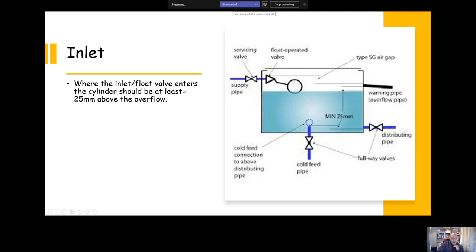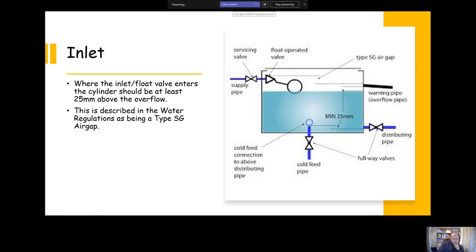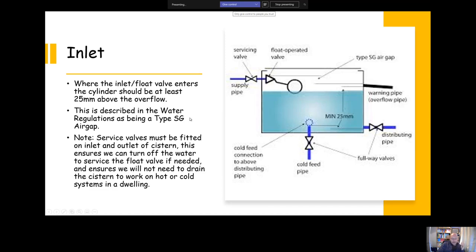For inlet, our inlet should be at least 25 mil above the overflow. Like I say, 25 mil is a key number for systems. If you get any questions in your test, if in doubt, pick 25. It would have an SG air gap, which basically means you've got a round overflow with at least 25 mil of a gap between the inlet and the overflow. The overflow should be sized to make sure it can cope with the flow of water should the inlet control device fail. Basically, you'd make it one size larger than the inlet. So if you have a 15 mil pipe coming in, you'd have a 22 mil overflow. If you had 22 mil pipe going in, you'd have at least a 28 mil overflow. Service valves, as I've already said, would be fitted on the inlet for servicing of the float valve and on the outlet so you can work downstream without having to drain the whole system.